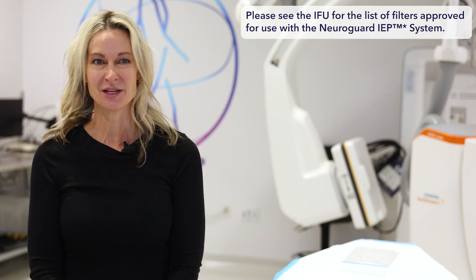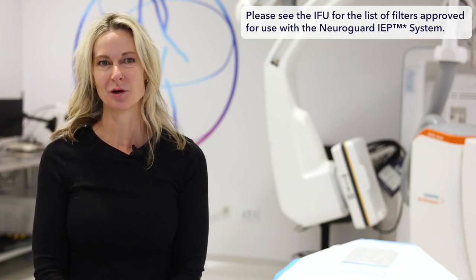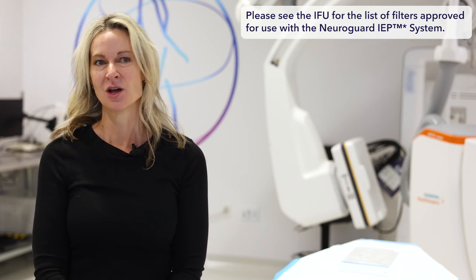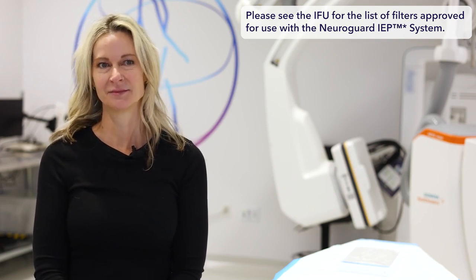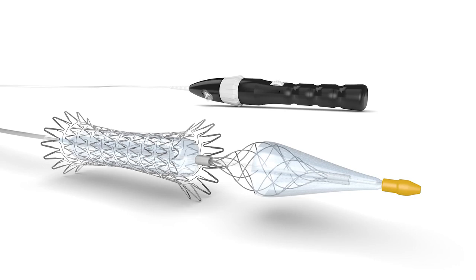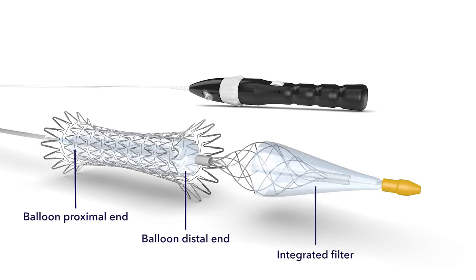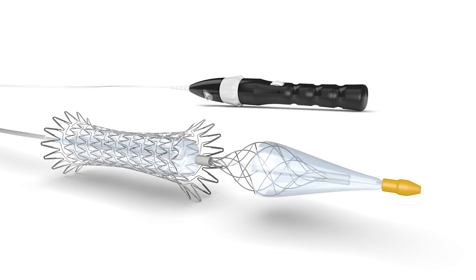The system is rapid exchange and is compatible with commercially available primary distal embolic protection devices with an 0.014 diameter guide wire. It consists of a multi-lumen shaft with an inflatable semi-compliant angioplasty balloon at the distal end and handle at the proximal end. Distal to the angioplasty balloon is an integrated filter in the baseline collapsed state. A nitinol self-expanding stent is preloaded on top of the angioplasty balloon. Both the stent and filter are covered by an outer sheath. The system includes multiple radiopaque marker bands.